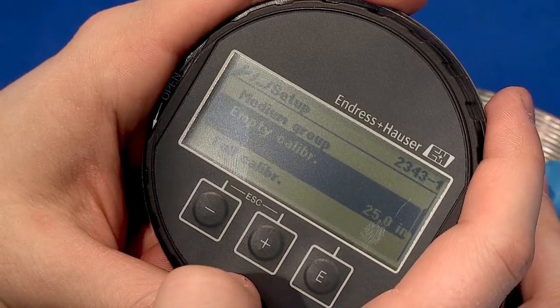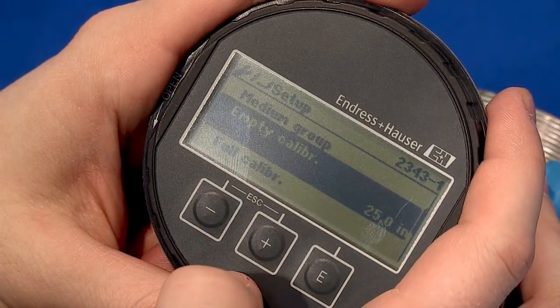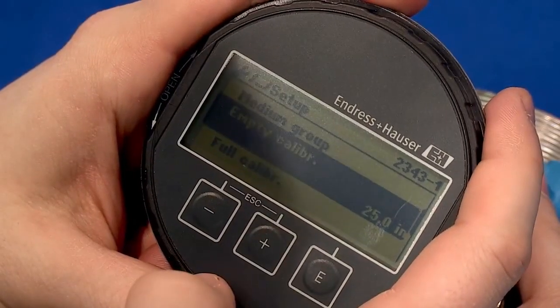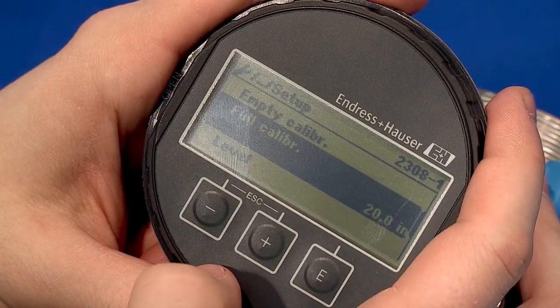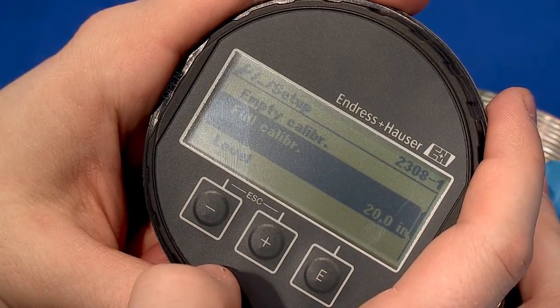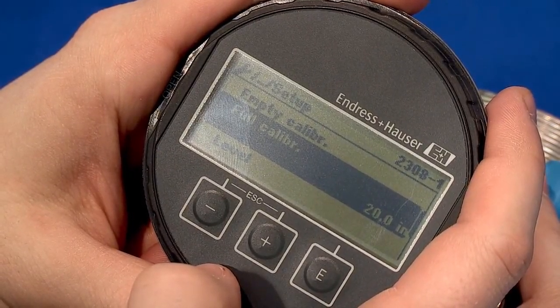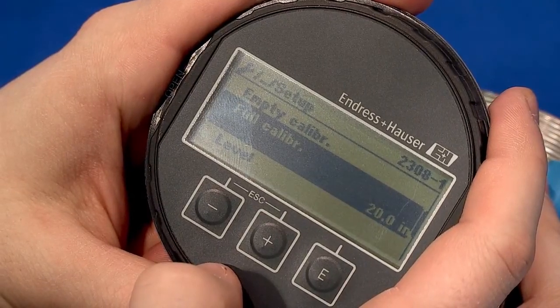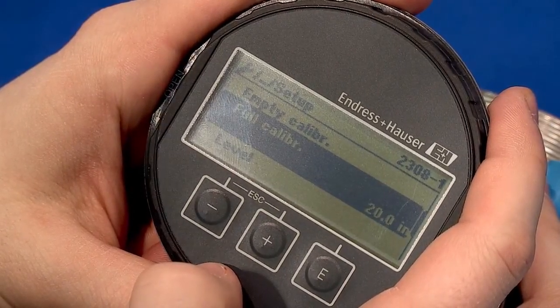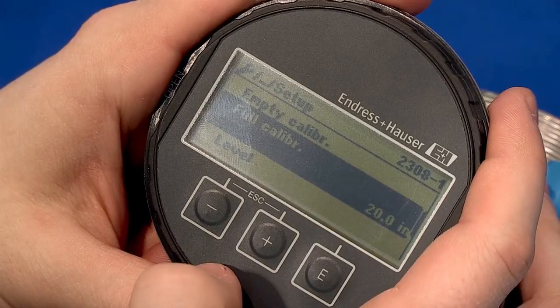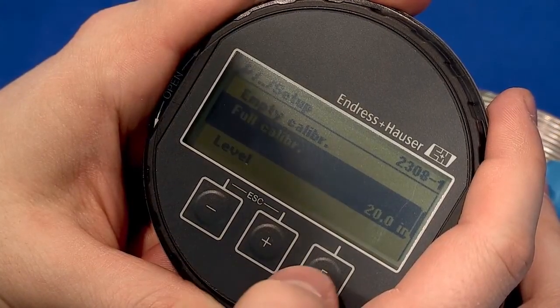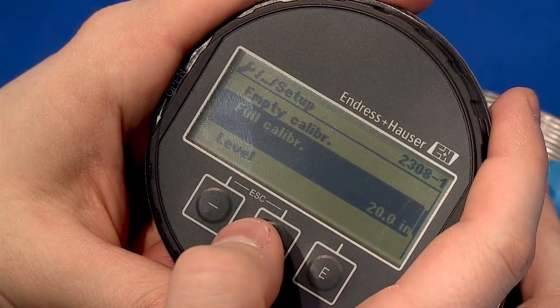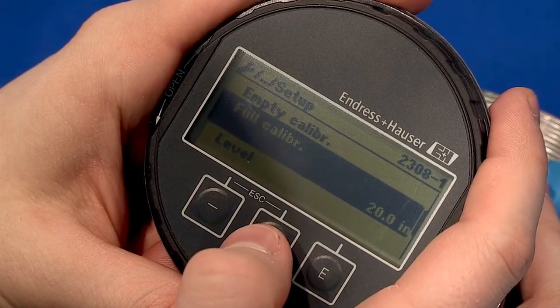Once the empty calibration value has been entered, you will then need to enter the full calibration value. This is the distance from your 0 point up towards the transmitter. This is the span of your instrument. This number will also never be 0. For our example, we will set our full calibration value to 20 inches. This sets our 100% mark 5 inches from the top.